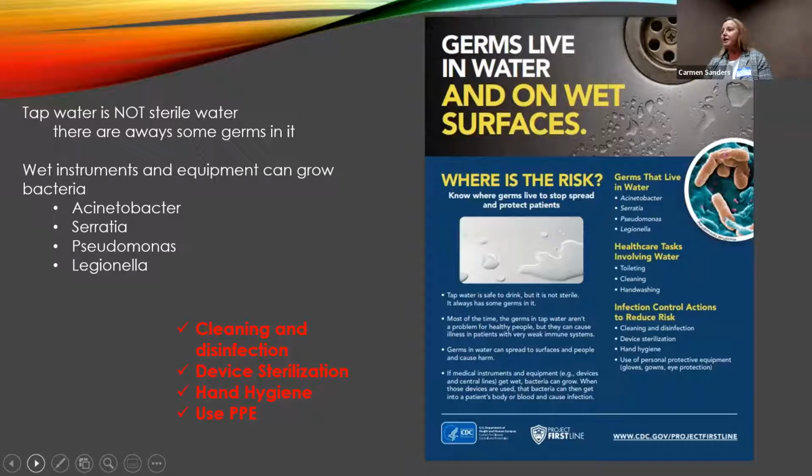So to get rid of those risks, we need to be cleaning and disinfecting. We need to do our device sterilization according to the manufacturer's IFUs, which is information for use. It comes with every product that we buy in the medical field, and it will teach you how to take care of it and exactly what it needs to be cleaned with, so it doesn't cause damage or corrosion or leave behind anything that doesn't need to be left behind.